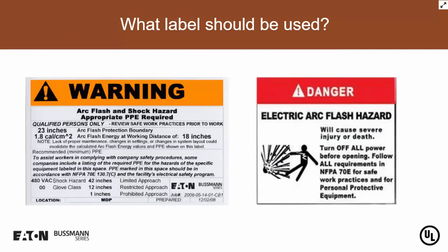All right, so the question you've got to ask yourself is, if my SCCR is adequate, so let's say my panel or machine has a 50 kA SCCR, and my available fault current is 40,000 amps, then what label would I put on it? Well, after I have completed the arc flash calculation, I could put the sticker on the left, and I stick that on my machine where electricians and OEMs know what to wear.